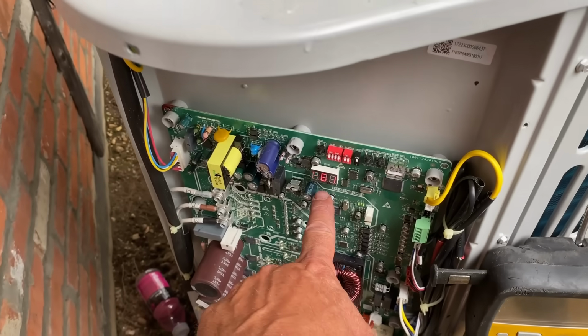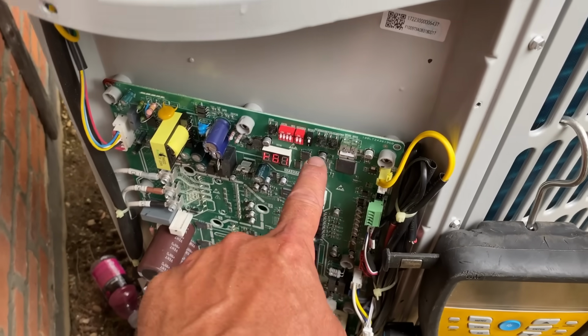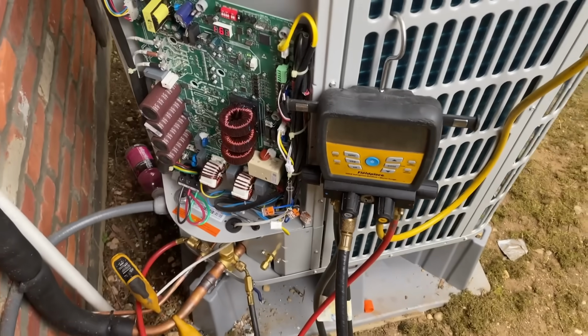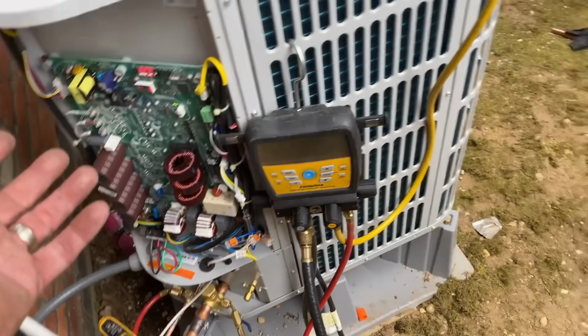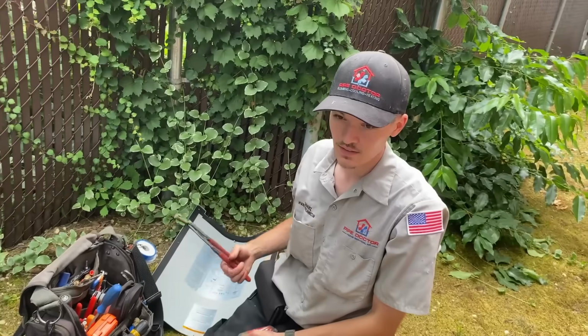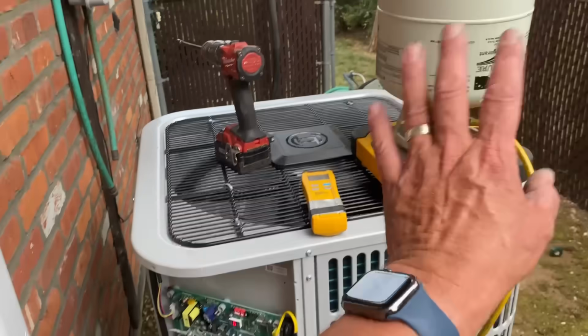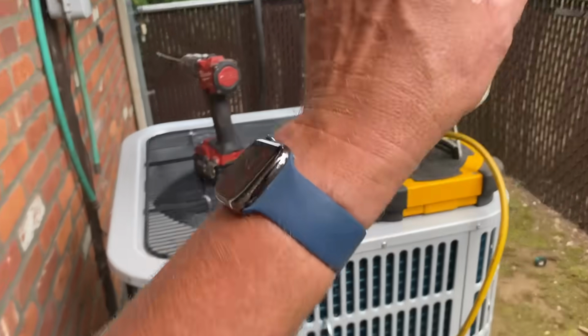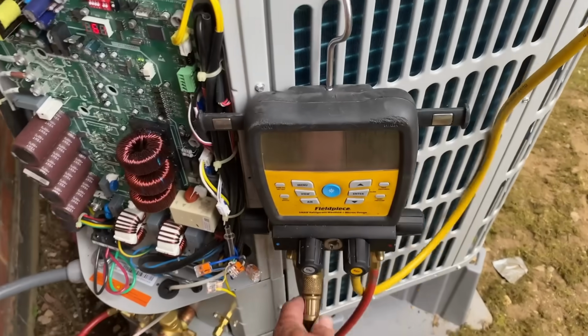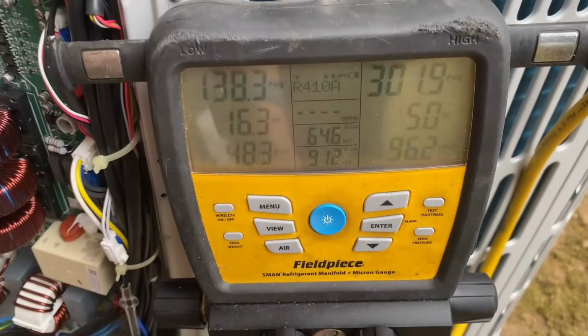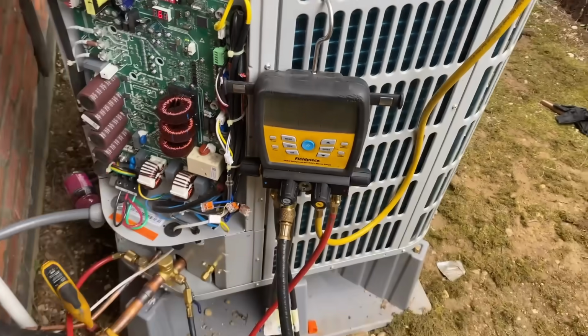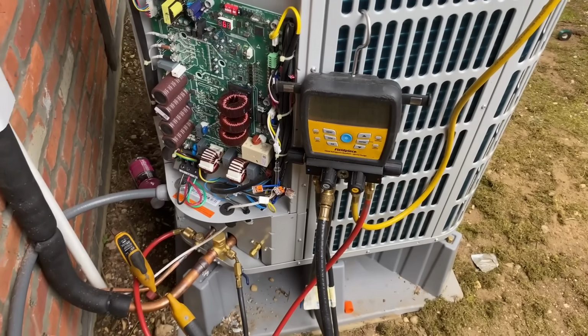And right now we're at a frequency of 61. We're in force mode because we need to charge up the system. We have 42 feet of line set. Yep, 42 feet of line sets. We're going to charge by distance, and then we're going to charge by subcooling. Make sure we get exactly 10 degrees of subcooling. Right now we're at 5.2, slowly climbing. May need to add a little bit more, 5.3.